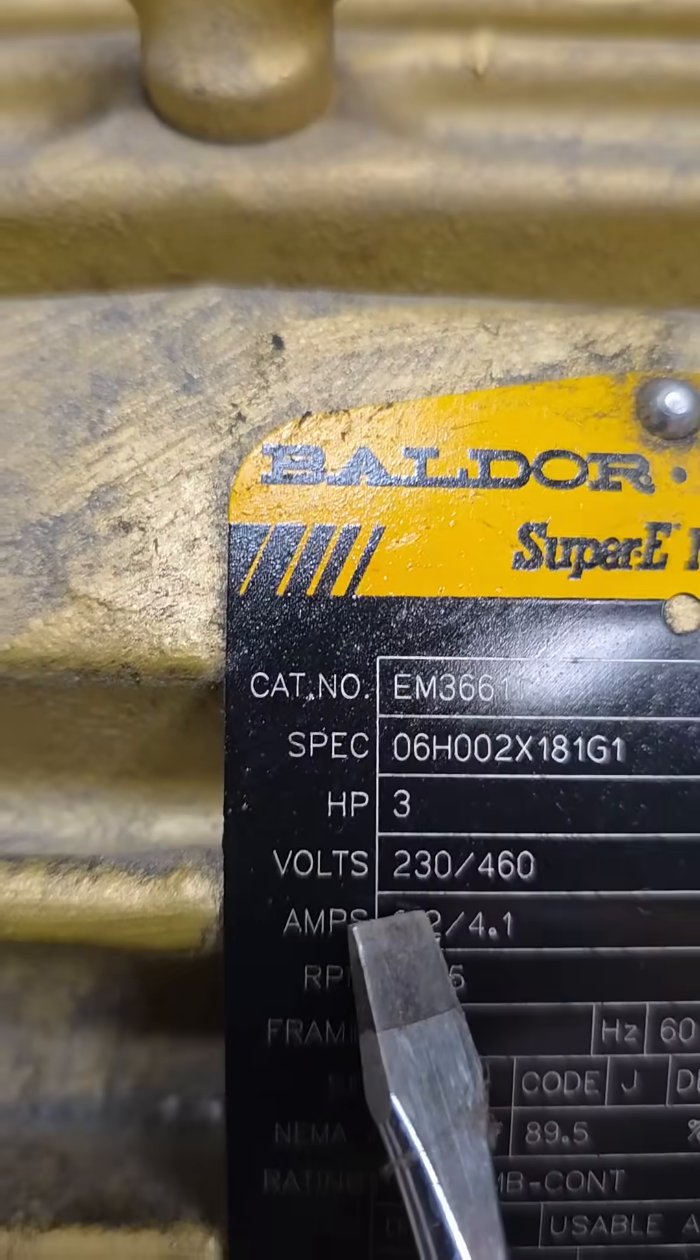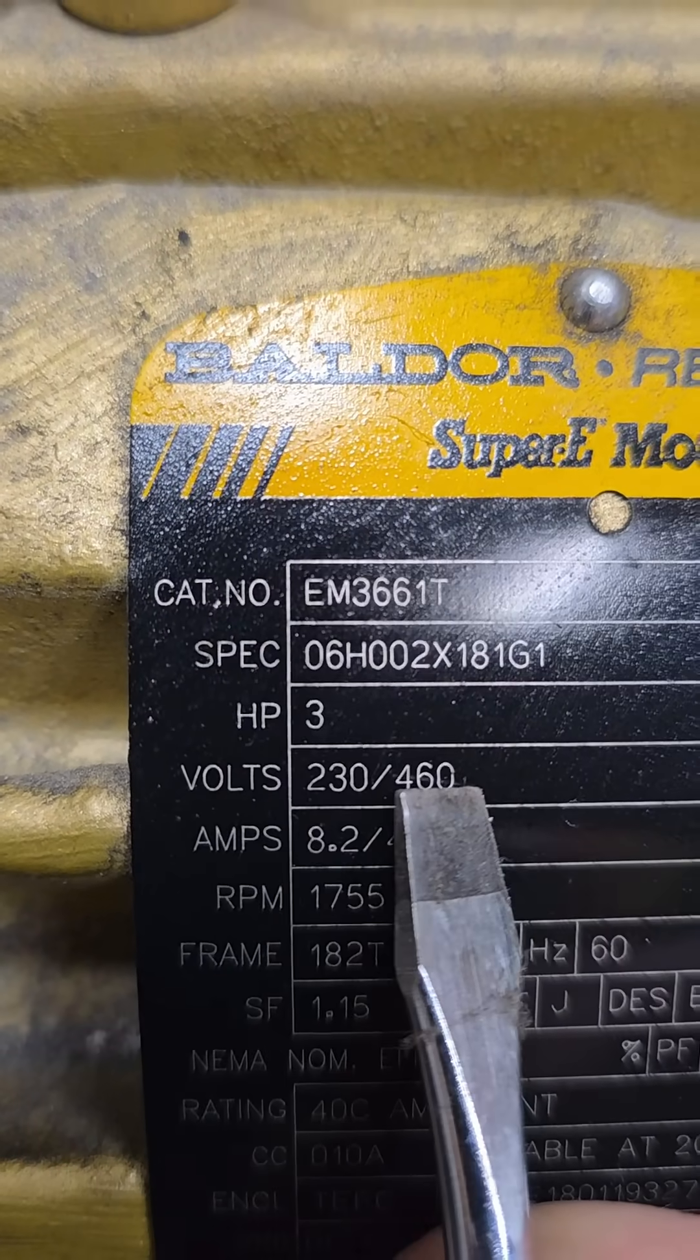Well, how do I know what's high and low voltage? Well, that's a good question, and that's where your nameplate comes in. So right here under volts, my nameplate will say 230 and 460. So I automatically assume that the lower number is the low voltage and the higher number is the high voltage.